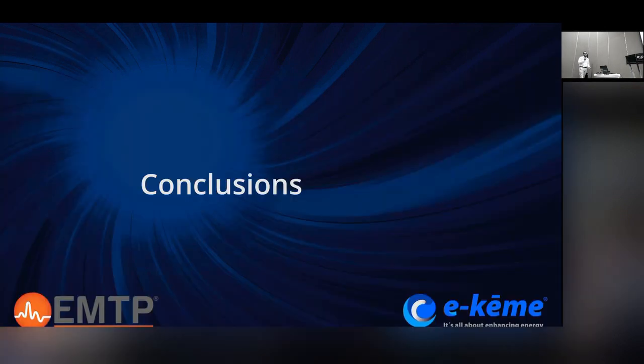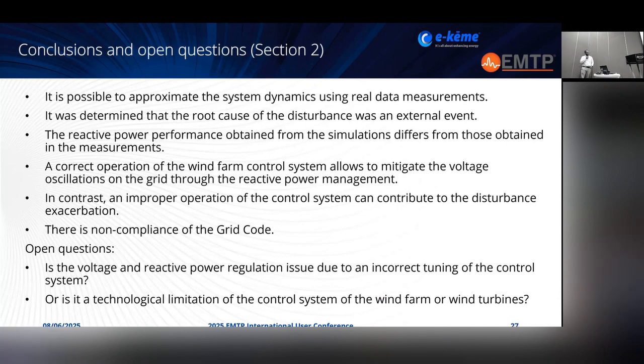So here we jump to the conclusions of section number 2. It is possible to approximate the system dynamics using real data measurements. It was determined that the root cause of the disturbance was an external event, the trip of the transmission line. We can also see that the reactive power performance obtained from simulations differs from the measurements. This was due to the plant in simulation actually compensating the voltage oscillations. So we can also see a correct operation of the wind farm control system, and this allows us to mitigate voltage oscillations on the grid. In contrast, if we have an improper operation of the control, we can contribute to the disturbance, and this could be a point where the system destabilizes.